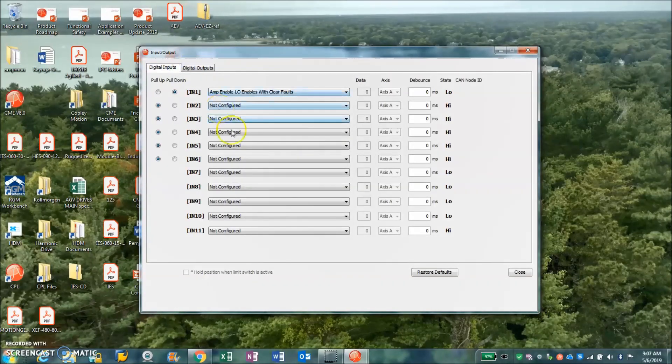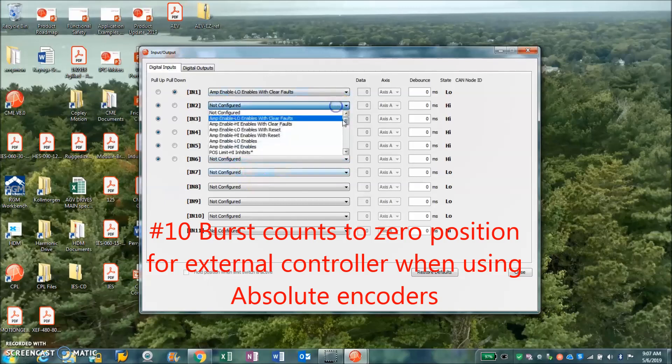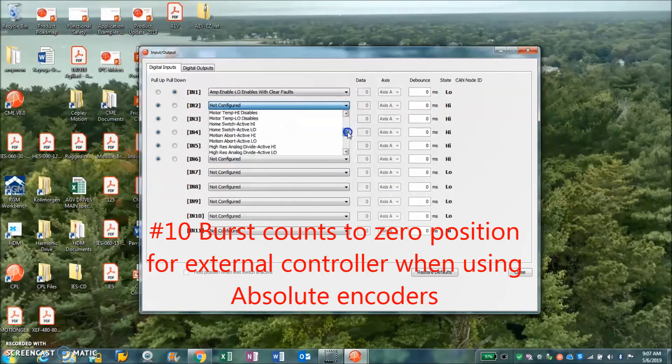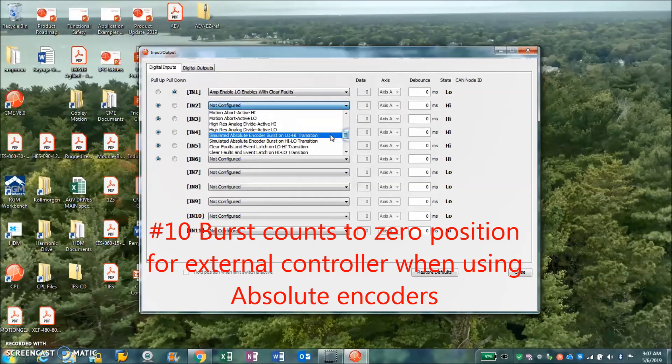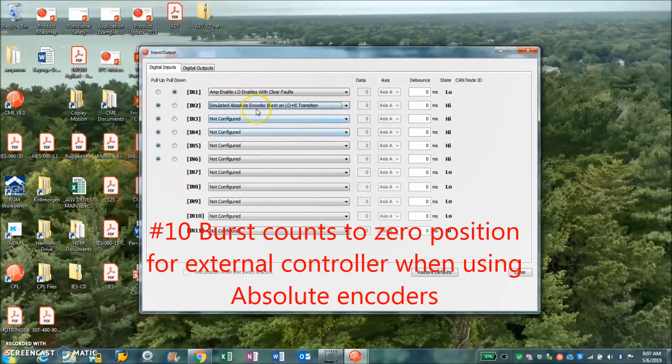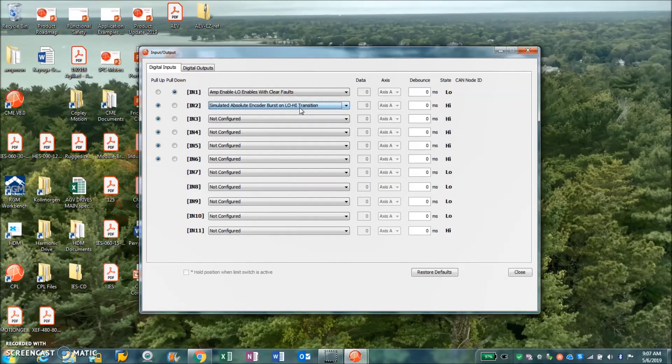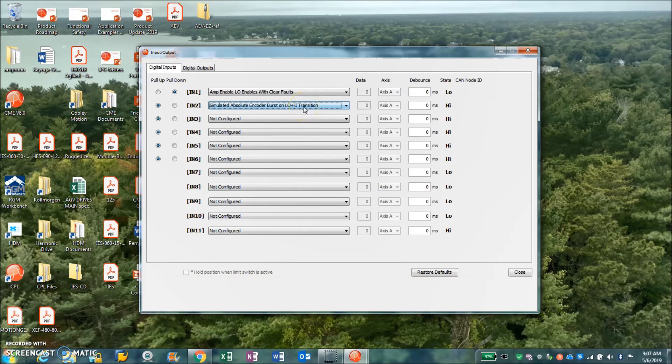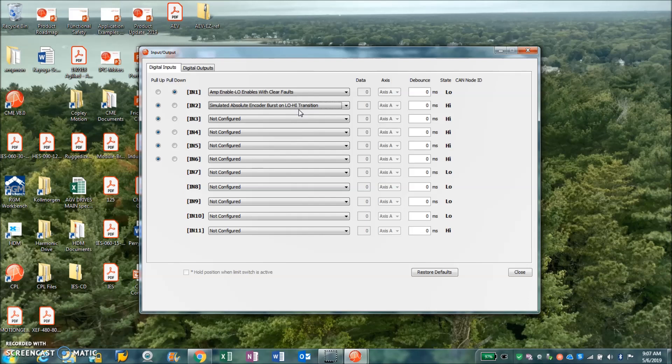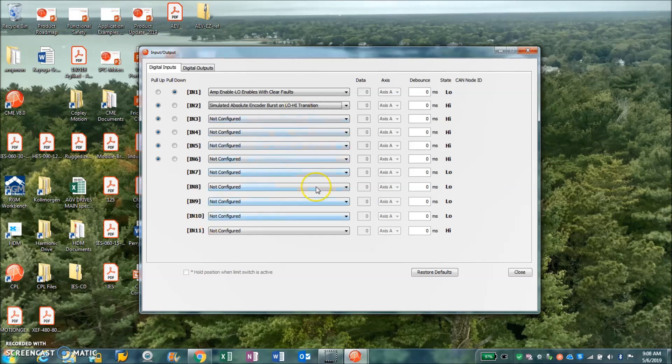And then of course the simulated encoder burst. So simulated encoder burst is an input, and when the input goes from a low to a high transition, if you have an absolute encoder and you're so many counts away from the zero position, this will burst out that number of counts at a certain frequency like a few megahertz. If you're really far from that position, it'll take a little while to burst out. But the burst is cool because this allows you to use an old style controller that needs to take care of counts, and you have an absolute encoder on your system. You want to know where you are with respect to zero - it'll burst out the pulses and say hey, I'm like a million counts away from zero, that's where I am. So that allows the controller to determine where you are.